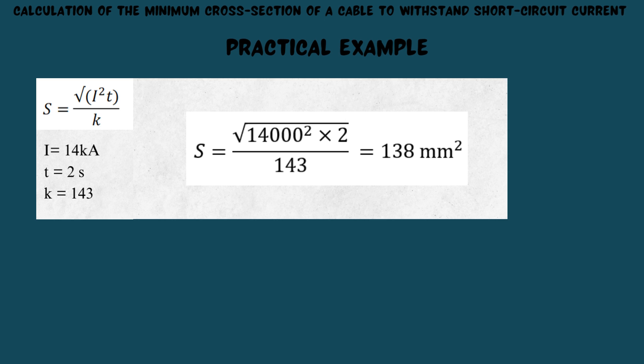When selecting a cable, the performance under fault conditions is an important consideration. It is important that calculations be carried out to ensure that any cable can withstand the effects of potential faults or short-circuits. The primary concern with cables under fault conditions is the heat generated and any potential negative effect this may have on the cable insulation.